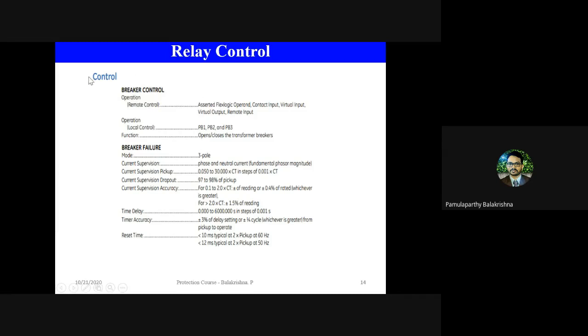If a device that is upstream, either a relay or SCADA or anything, wants to control the breaker, remote control should be enabled. If local control is enabled, then only the operator, by going near the relay hardware and pressing a push button, can control the breaker. Means manually he can open or close by pressing a push button. This is usually not done. Only the remote control mechanism is what is being executed. This is only done when you are testing the breaker, installing the breaker, or doing any maintenance action on the breaker. At that time you disable remote control so that nobody operates in an unauthorized manner and you have control over the breaker.